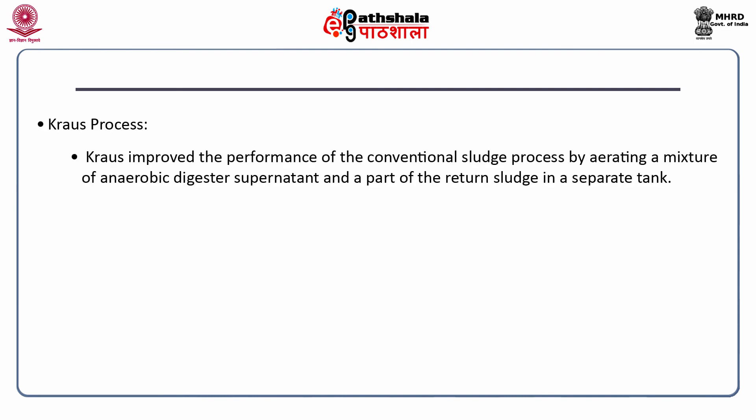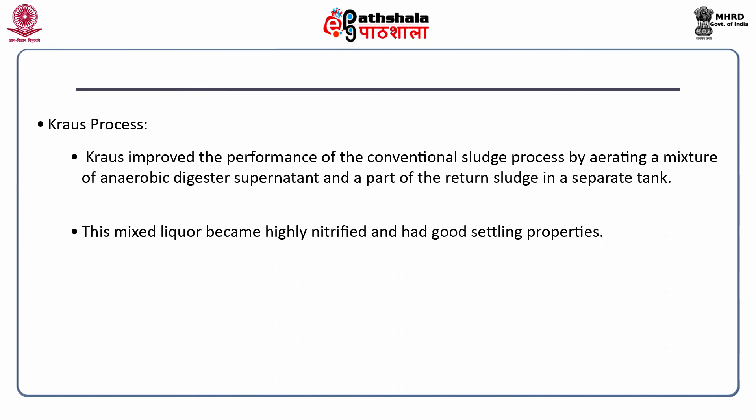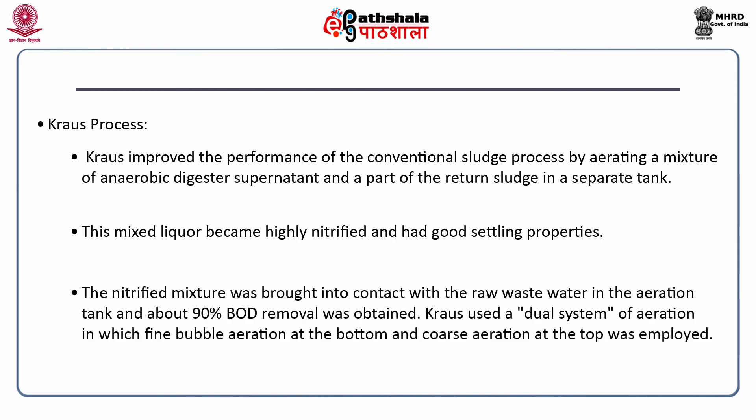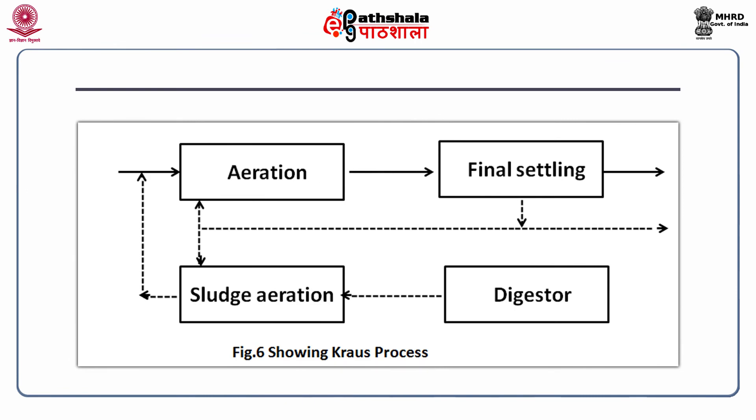Another modification is the Kraus process. This process improves the performance of the conventional sludge process by aerating a mixture of anaerobic digester supernatant and a part of the return sludge in a separate tank. This mixed liquor becomes highly nitrified and has good settling properties. The nitrified mixture is brought into contact with raw wastewater in the aeration tank and about 90% BOD removal is obtained. The Kraus process uses a dual aeration system with fine bubble aeration at the bottom and coarse aeration at the top. This figure shows the modification made in the activated sludge process while applying the Kraus process.